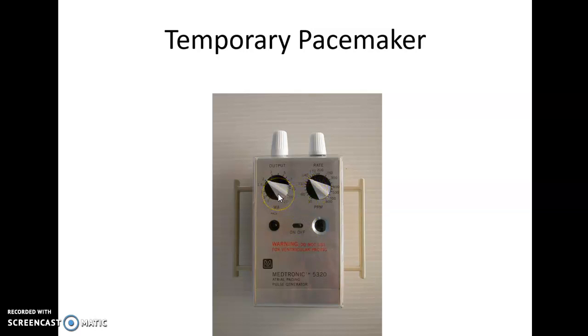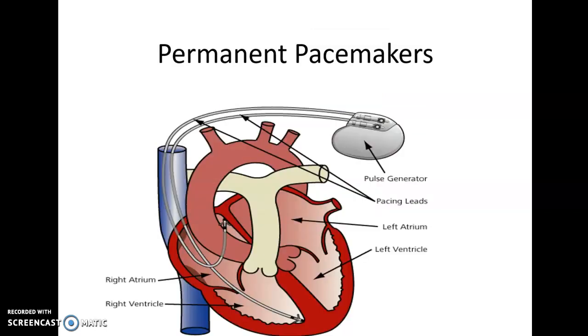And then the milliamps, or the output, you start turning that up until you see the pacemaker fire and until you see capture happen. Now, because this current is going directly through a wire and going directly into the heart, generally this is only going to take 8 to 10 milliamps of current to get capture to happen, where with our external pacemaker, it'll frequently take somewhere from 40 to 80 milliamps of current before you have a capture happen.